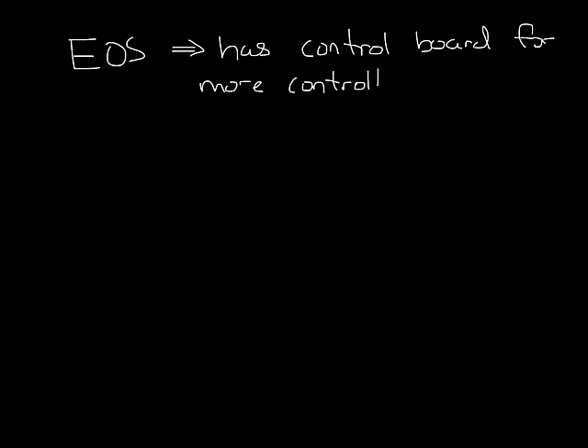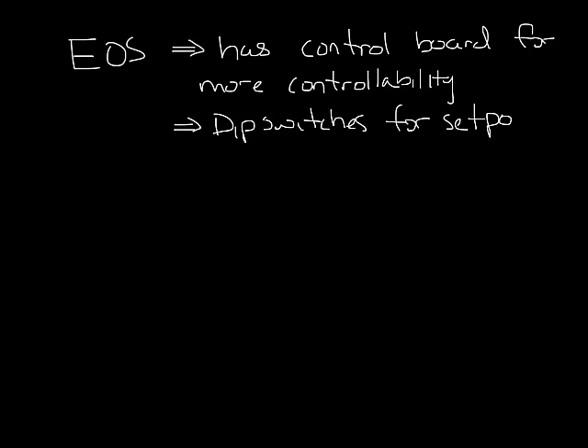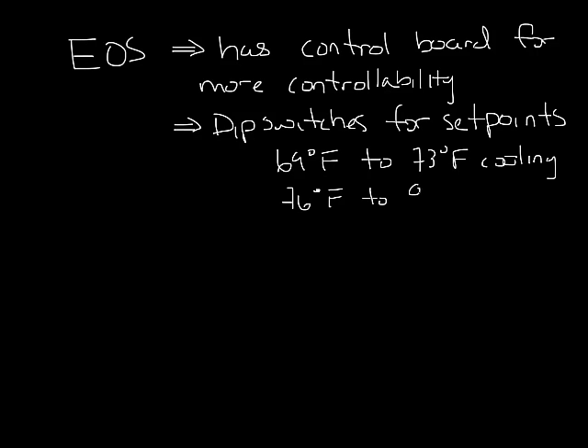Titus also makes an auto changeover slot diffuser that has more controllability called the EOS. The EOS has a small control board that allows you to use dip switches to set the heating and cooling set points. The set points can be set anywhere between 69 and 73 degrees for cooling and 76 to 80 degrees for heating.